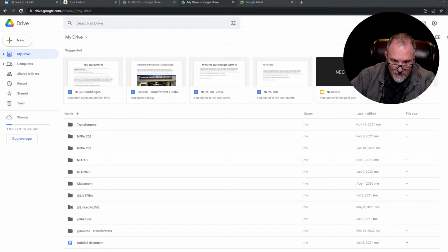You know, it's interesting that we talked last time I was on with you about that fault current, because they added that 7th item into that 130, the old 130.4. That fault current is going to catch a lot of people by surprise. Remember, 2 weeks ago, we talked about adding that 7th item to that 6-item list. There are 6 items in there now. They're adding a 7th one that says that the equipment is rated for the available fault current. There are so many places that have no idea what the fault current is. They have no idea how we'd even figure it out. Yep.